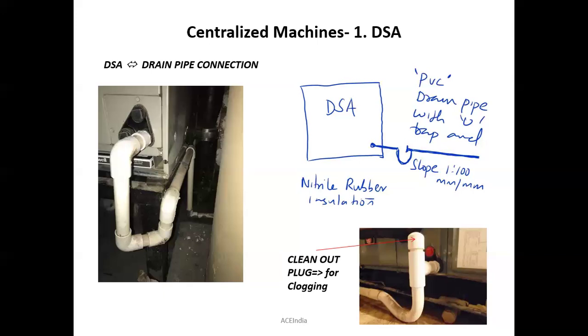So in order to rectify that problem, we need to provide some kind of slope for those pipelines, especially the drain pipelines. Generally, the slope is termed as something like 1:100, which means for each 100 millimeters of distance of your pipeline, you need to provide 1 millimeter offset, which means a slope. Okay. Then once again, the other mandatory thing while providing a drain pipe connection is to attach a U-trap.